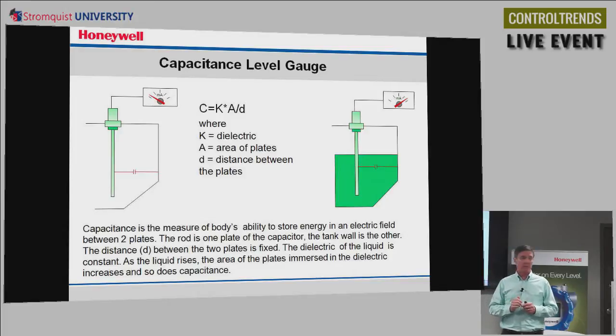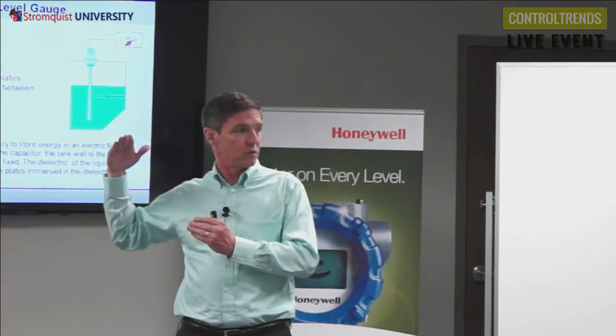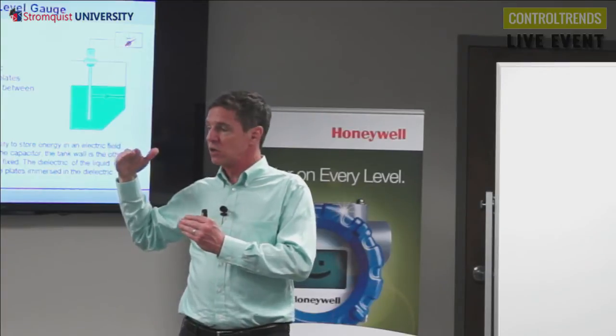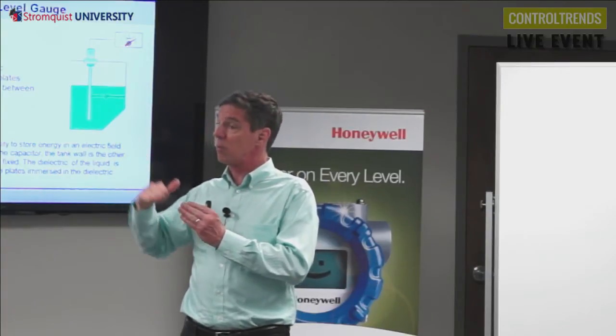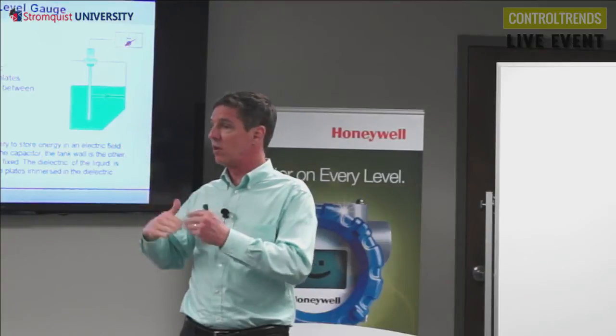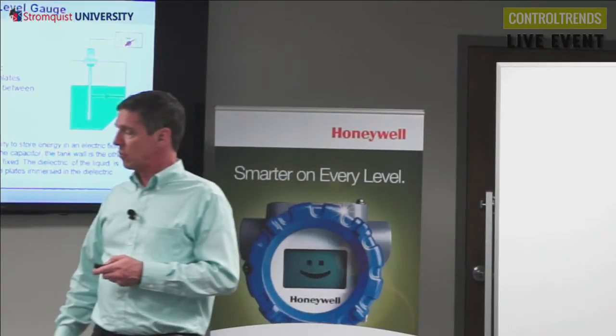So the way we make a capacitor in a tank is to say that the rod of the capacitance probe is one plate, and the tank wall is the other plate. With nothing in the tank, there's really no capacitance. But as you fill that tank up with a material that has some sort of dielectric constant, that is what increases the capacitance. So as the level changes, the capacitance changes. That's how capacitance level gauges work.